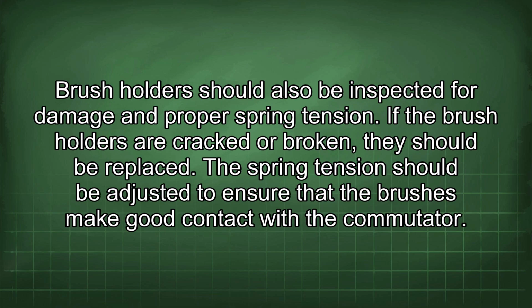Brush holders should also be inspected for damage and proper spring tension. If the brush holders are cracked or broken, they should be replaced. The spring tension should be adjusted to ensure that the brushes make good contact with the commutator.